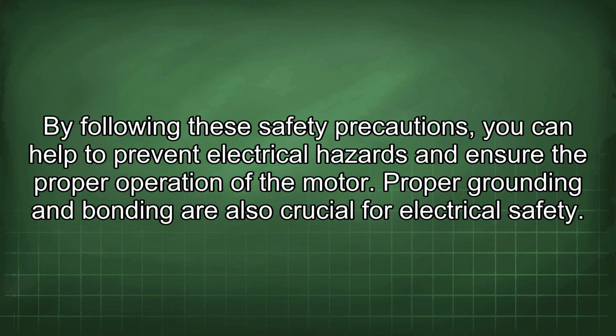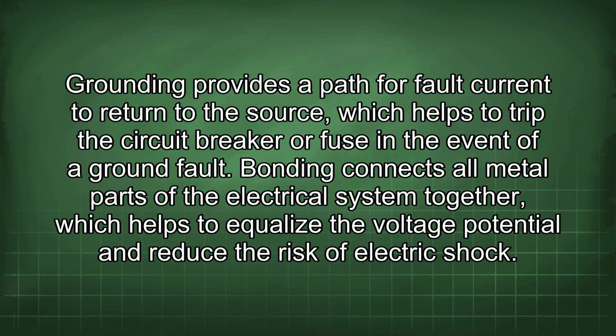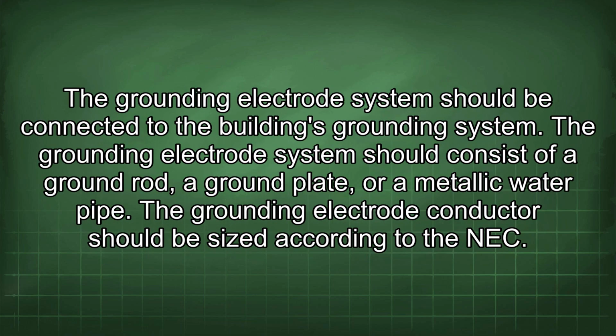Proper grounding and bonding are also crucial for electrical safety. Grounding provides a path for fault current to return to the source, which helps to trip the circuit breaker or fuse in the event of a ground fault. Bonding connects all metal parts of the electrical system together, which helps to equalize the voltage potential and reduce the risk of electric shock. The grounding electrode system should be connected to the building's grounding system.